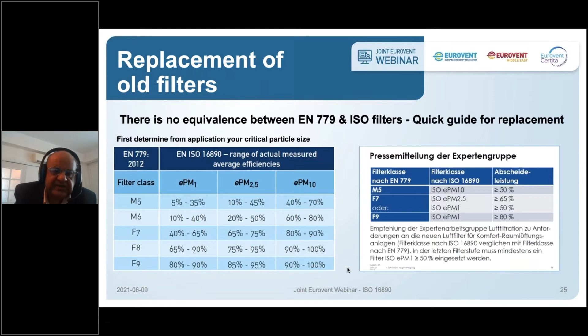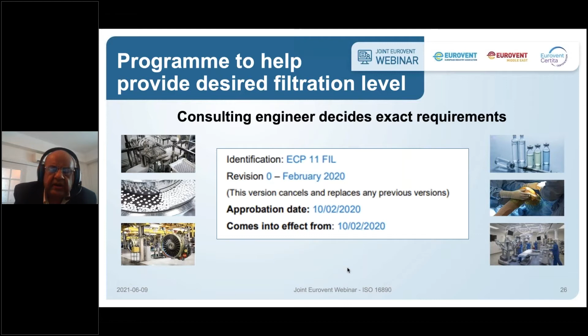ECC, or Eurovent Certita certification, has come up with a very good program, ECP 11 FIL. It kicked in 2020. We need to make it a success, basically, and it's very important that filters deliver what they state, and that's what you get through certification. You can be assured of the quality of filter you are putting into your system. Then it's a job to measure the outdoor PM levels and indoor PM levels, tweak things, do what is necessary, and get your indoor air quality levels right at the right energy spend.